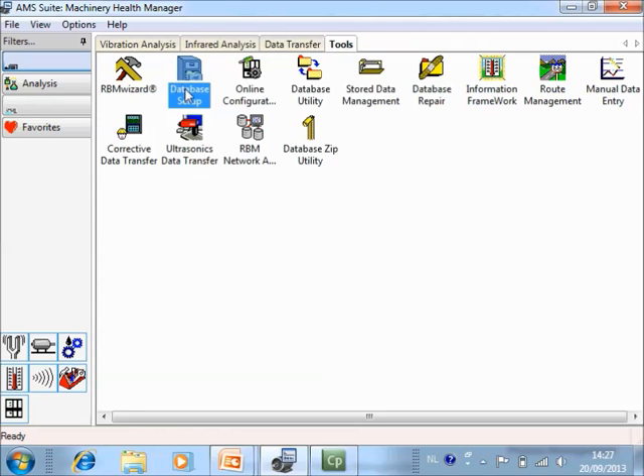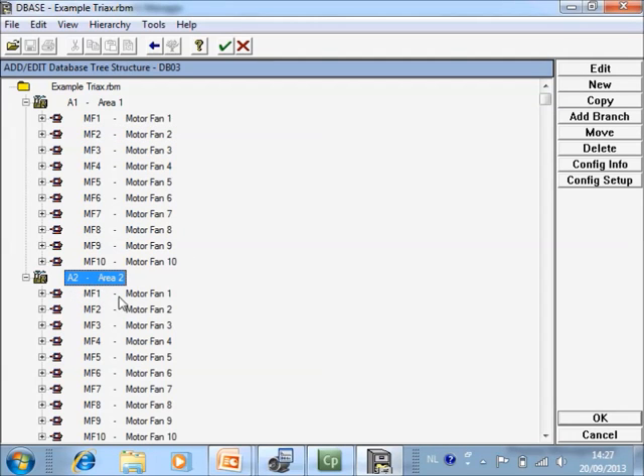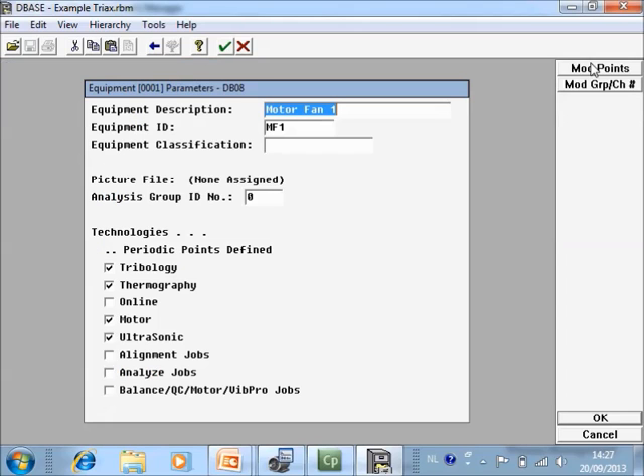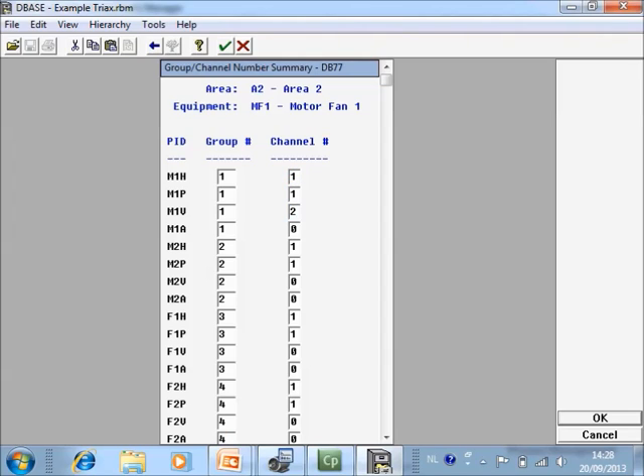In the software I go to Tools > Database Setup > Tree Structure. I select the machine, then Edit > Modify Group Channel. Here you can see how the RBM wizard has configured it. We change this so that motor outboard is plane 1, group number 1; motor inboard is group 2; fan inboard is group 3; and fan outboard is group 4. Horizontal and peak view are always channel 1, vertical is channel 2, and axial is channel 3.